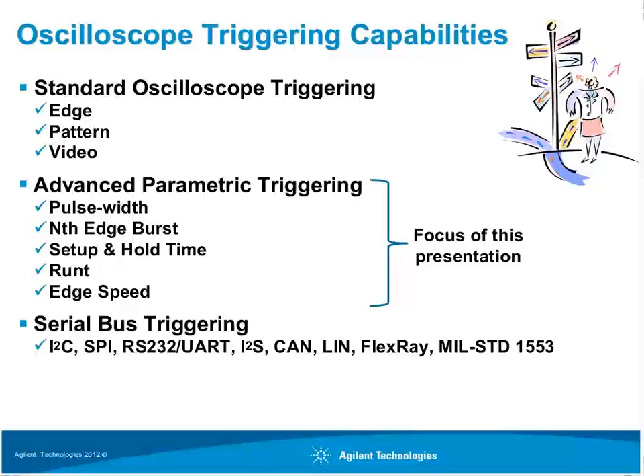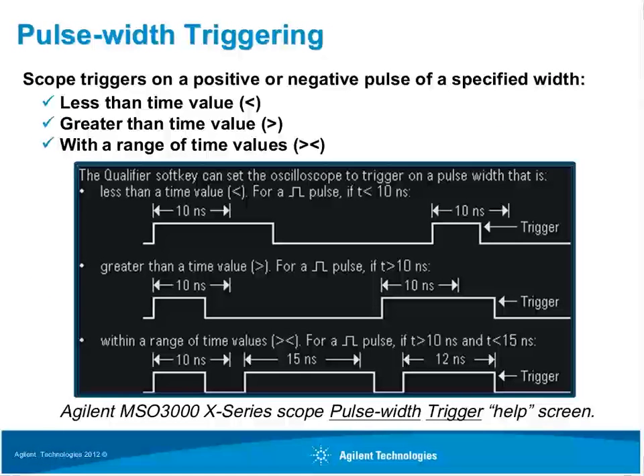Although edge triggering is the most commonly used type, many of today's oscilloscopes have advanced triggering to synchronize acquisitions. With advanced parametric triggering, we have pulse-width triggering, nth-edge burst triggering, setup and hold, RUNT, and edge speed — all of which will be covered in this presentation. This oscilloscope also comes with serial bus triggering, with a variety of serial protocols offering triggering capabilities specific to each protocol.